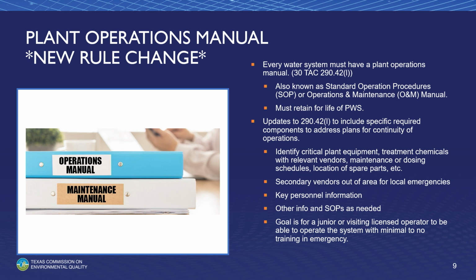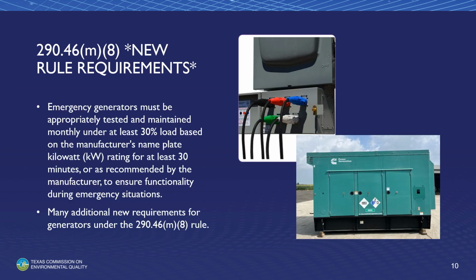Knowing your local water systems is also good for being able to share equipment or chemicals in a time of need. But yes, any other key SOPs, key personnel, that information's good to know. In the spirit of new rules, this is also a new rule, so generators, operating those under loads and the different variations of it. Within the new 290-46-8 rule, we have it very fleshed out of all the little specifics that are needed there, so I would definitely recommend going and taking a deep look at these new rules. More than just this 30% load once a month.